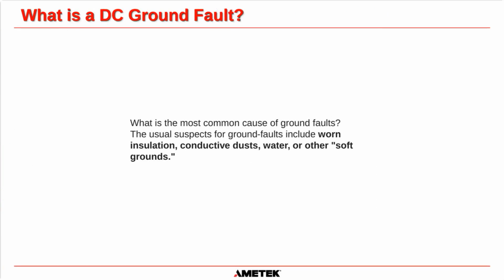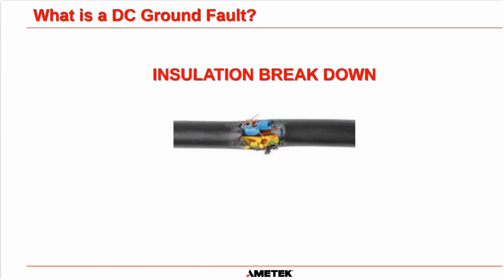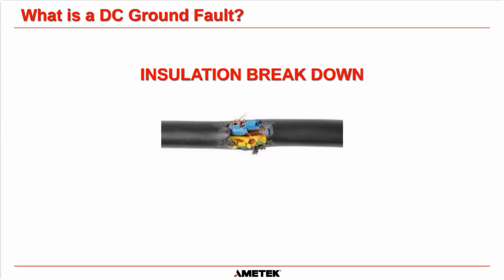So what are the most common causes of ground faults on DC systems? And actually, I should have made this clear before I started. We're not talking about AC ground faults. That's a different subject altogether. Maybe I'll do a webinar on it, but I'm not as familiar with AC ground faults as I am with DC ground faults. So the usual suspects for DC ground faults include worn insulation, conductive dusts, water, or other soft grounds. Okay, so insulation breakdown is when the insulation on the outer sheathing of a cable breaks down and the inside conductor is exposed to touching ground, basically.